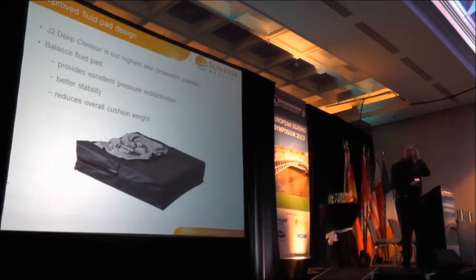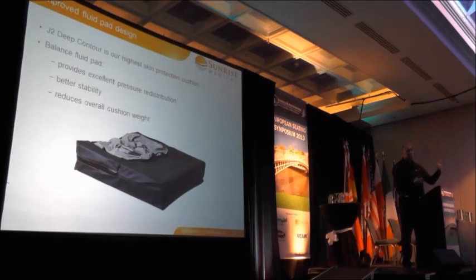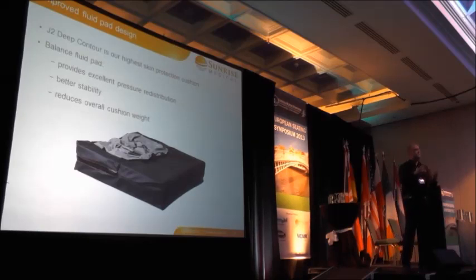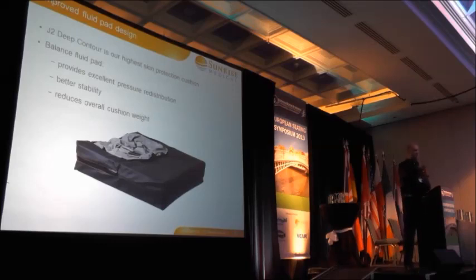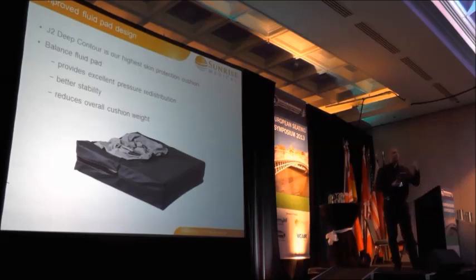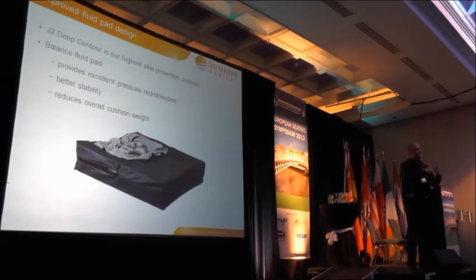When the J engineers designed this cushion, the real aim was to offer pressure relief comparable to what we'd associate with a J2D contour cushion. They used a pressure mapping rig system to achieve those readings. We see this cushion performing very similarly, with a slight difference at the greater trochanters where we're loading a little more for stability. So we get that high skin protection combined with stability — a cushion that offers the very good attributes of the J2D contour but in a much more stable base.